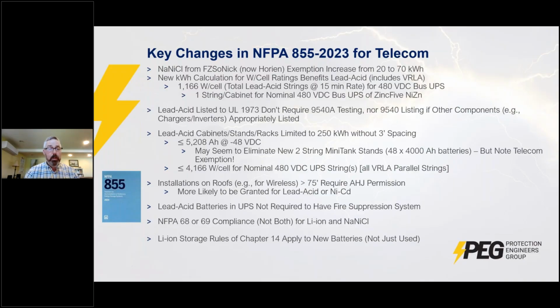Another point that's unique to lead acid is that you don't have to have a lead acid system level listing. If you have a listed UL 1973 lead acid battery and the other components that you're using with it, the charger and the inverter, are listed. Most ESS systems, this standard is going to say, have to be listed specifically to 9540, which is the UL listing standard for energy storage systems.